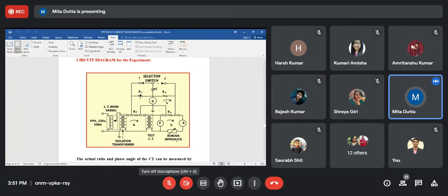And this is burden. Here we have used in the experiment, the burden is a resistive burden. We are using here a variable rheostat. And this is the test CT. The supply is the primary winding of a transformer is connected to the secondary winding of an isolation transformer, and the secondary winding is connected with RS and burden in series.